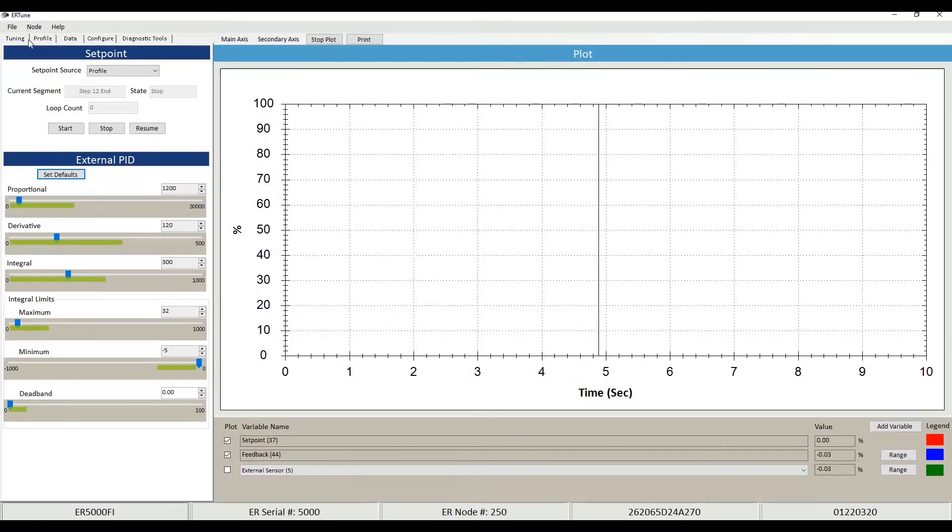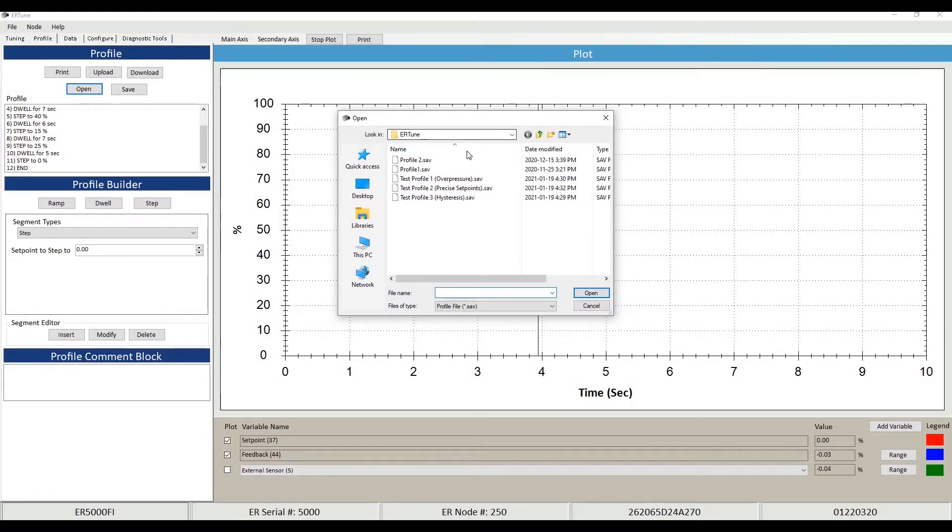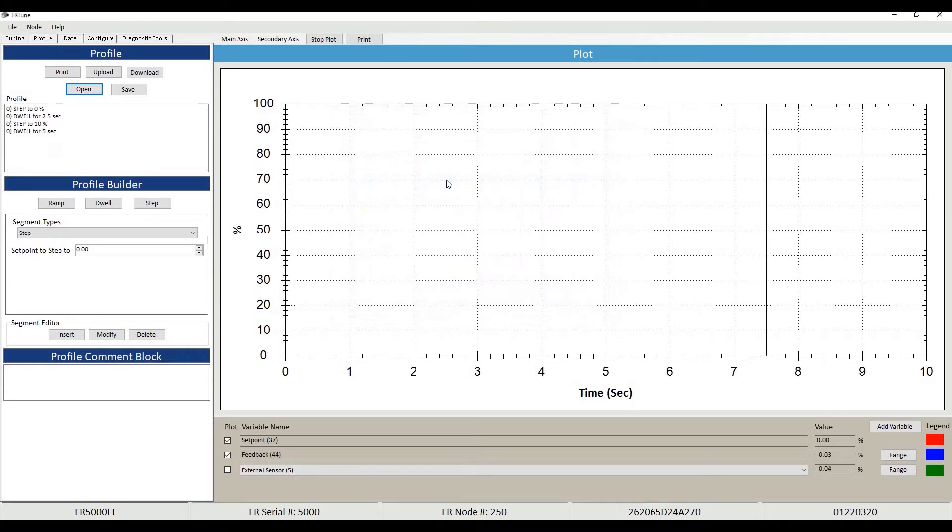I'm going to go to the profile tab in our ERTune software. I have a few profiles made up for this video. We'll jump in with test profile number one, which I've called 'Over Pressure.' An over pressure scenario is when you have a regulator set at a certain set point — in this case 10% — and you need it to stay there. If it goes above, say up to 26% of its range, you're going to have a PSV go on your line, and you'd have to send someone out to get it reset. We'll operate at 10% of its range as our set point.